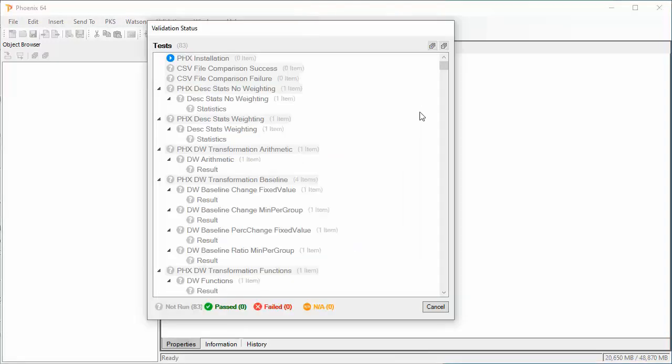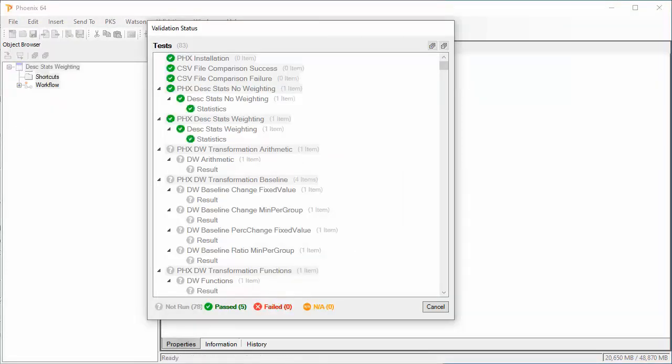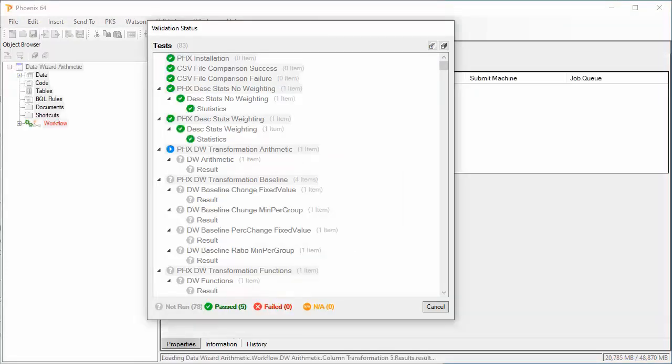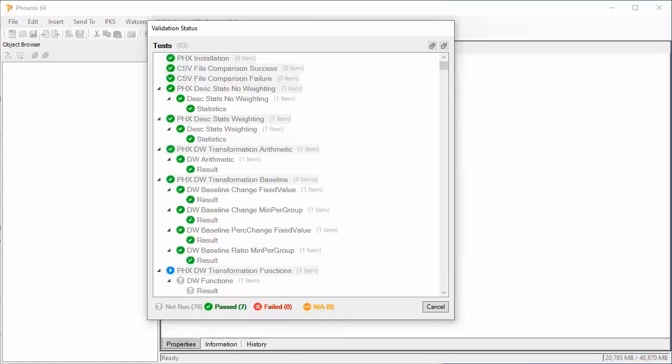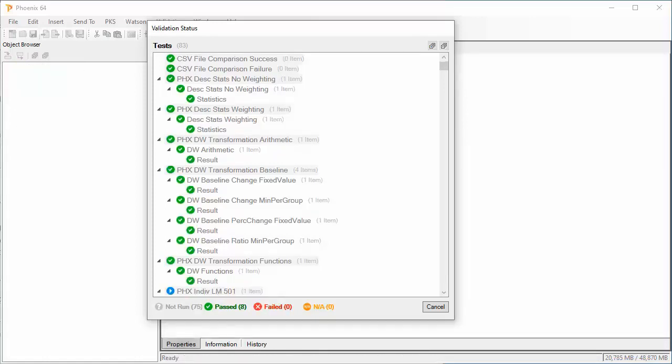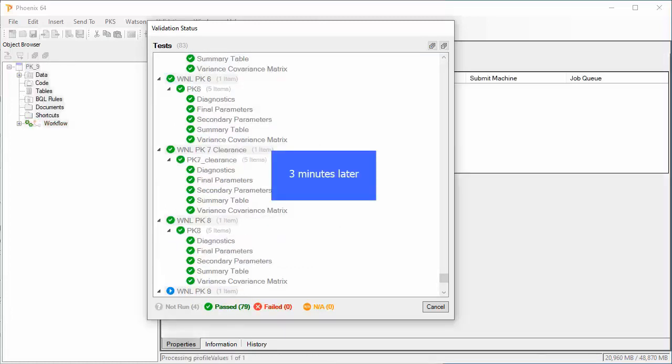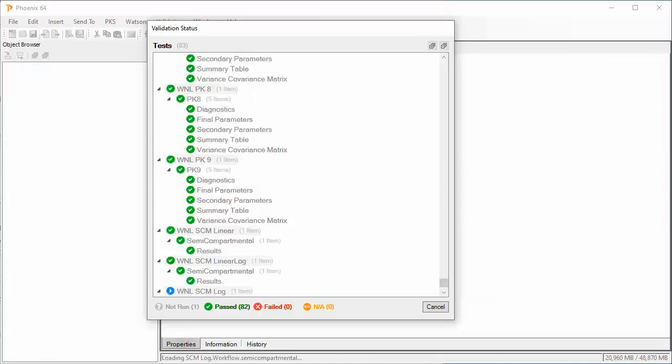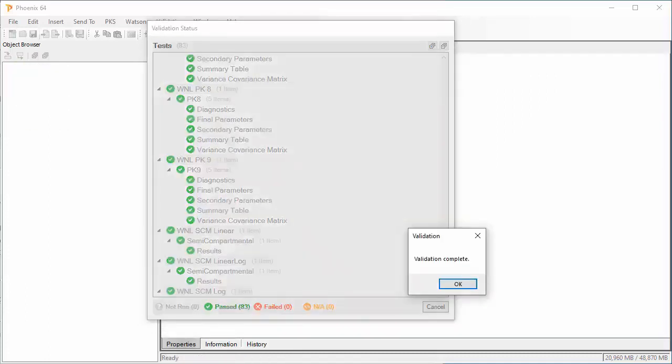The 82 different Validation tests proceed automatically. The average time to run the test is well under 30 minutes, but this machine has a solid state drive, so it is much faster. We are notified that Validation is complete, and then Phoenix generates the report.